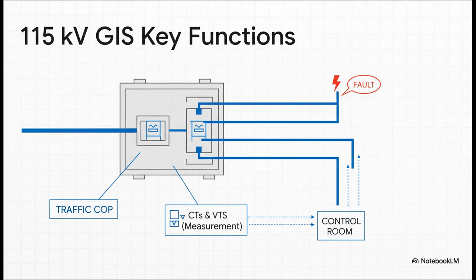So what does it do? Well, the GIS is basically the high-voltage traffic cop. It uses circuit breakers that operate at lightning speed to protect the grid and isolate any problems in milliseconds. It also has these tiny, super precise transformers built right in to constantly measure the electricity flowing through it, feeding all that data back to the brain of the substation. It's really the first line of both defense and control.